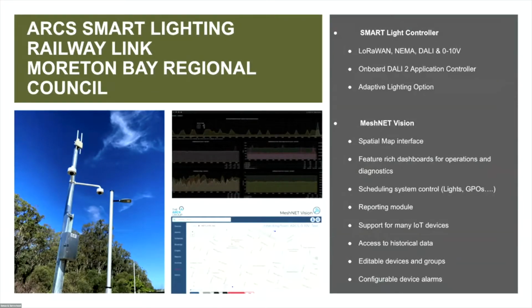We were given a task to create an adaptive lighting solution for that pathway. We had an existing LoRaWAN light controller, however it didn't fit the purpose, so we developed and extended our current range to include a LoRa-based NEMA DALI 2 controller. The differentiator for this controller is it has a DALI 2 application controller on board - we believe it's the only one in Australia, if not the Southern Hemisphere.